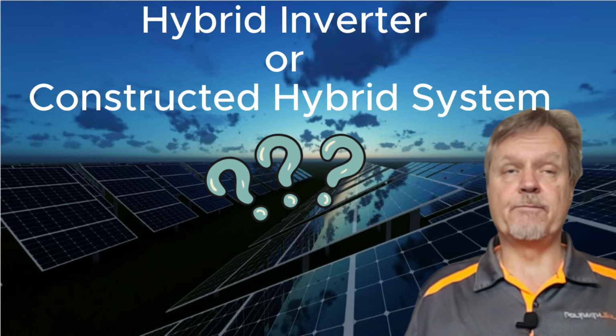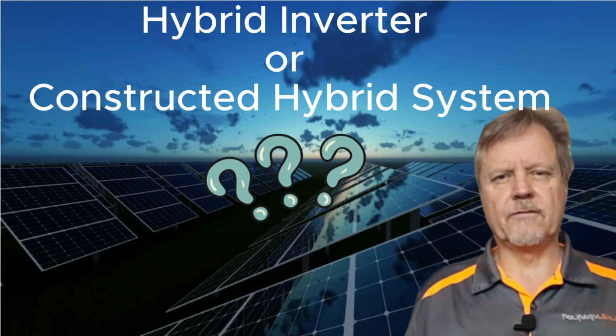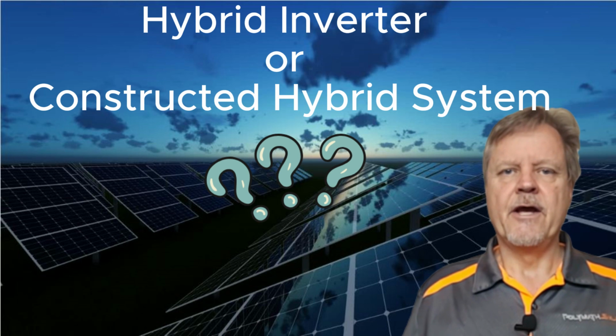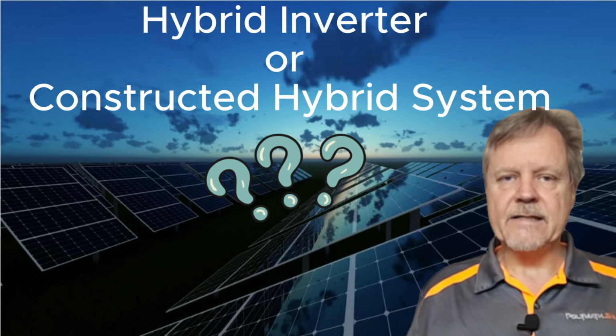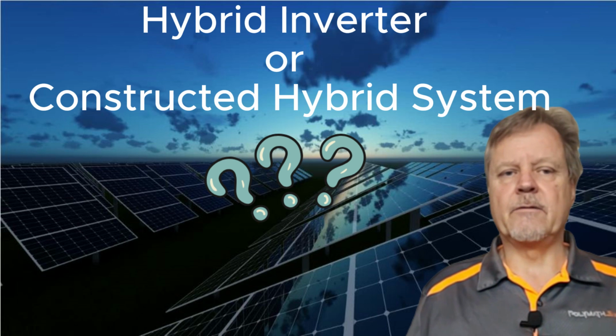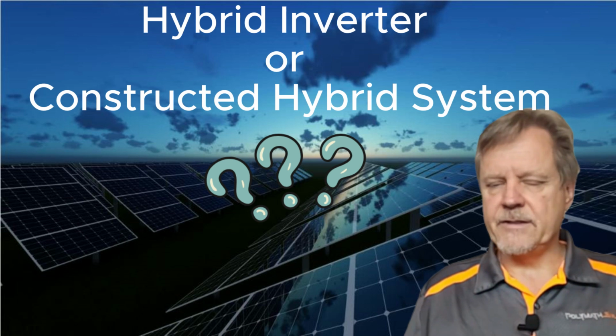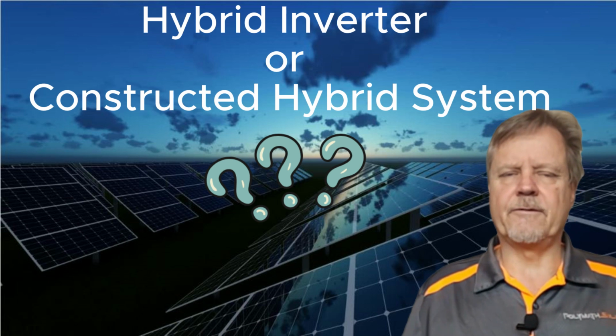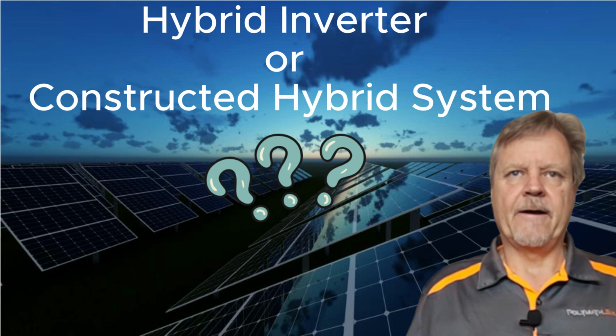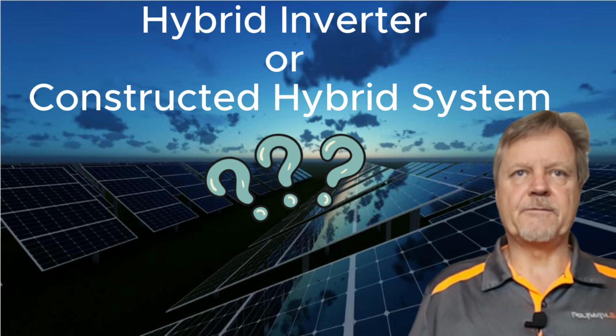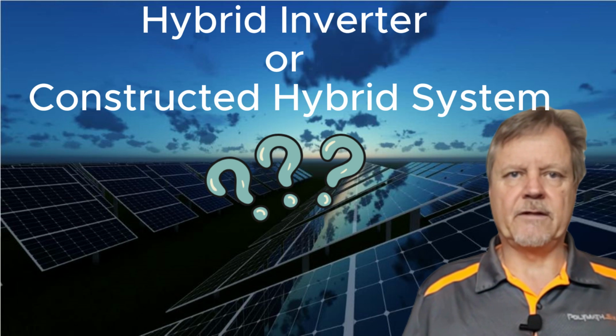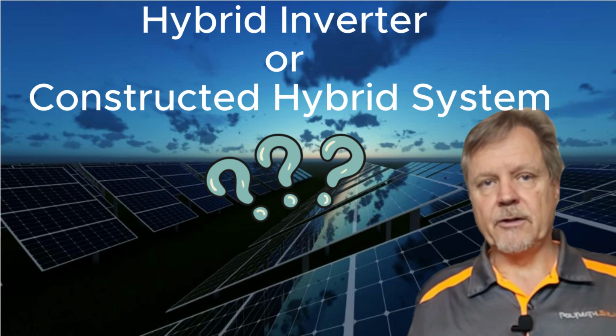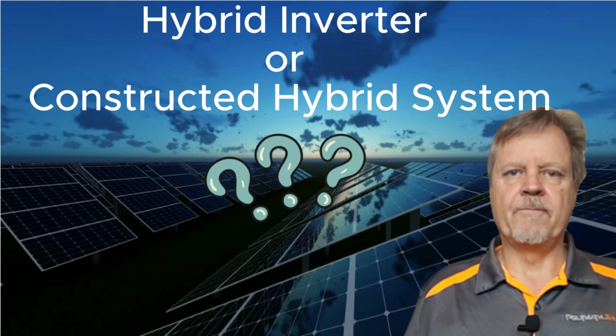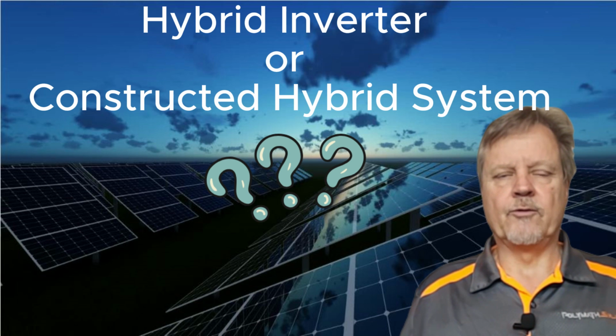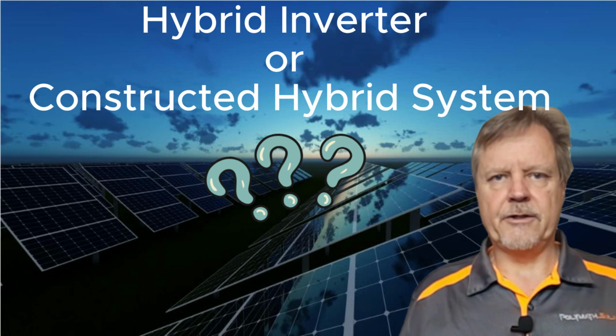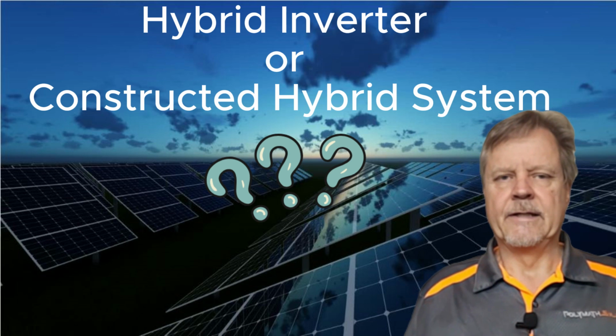There's also the advanced programming option. With more advanced inverters, you've got 3 or 4 relays you can control. With software, you can program those to open and close at a different state of charge, or battery state, or load, which means you can switch the geyser on and off depending on how much PV comes in, or start and stop pumps depending on the battery state of charge. So you've got multiple relays inside your inverter that you can control with software to manage your house and optimize the use of your energy.